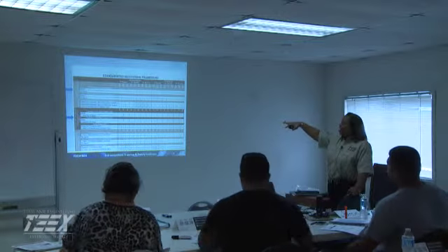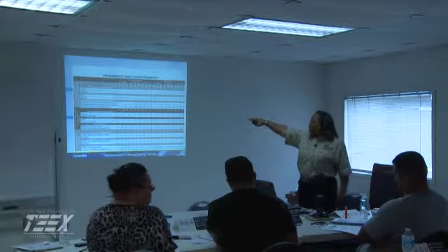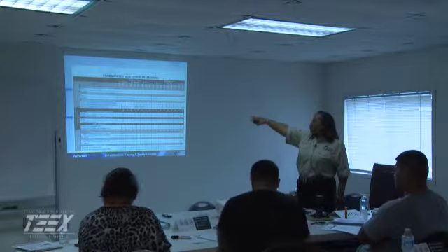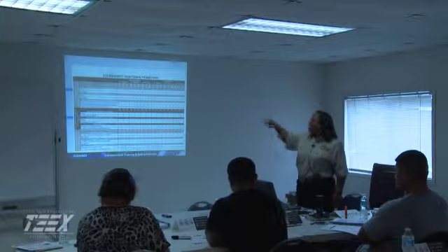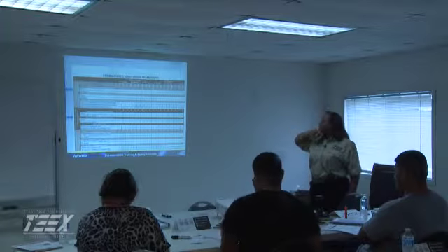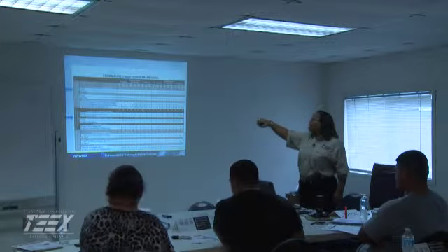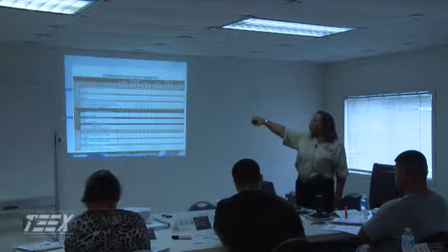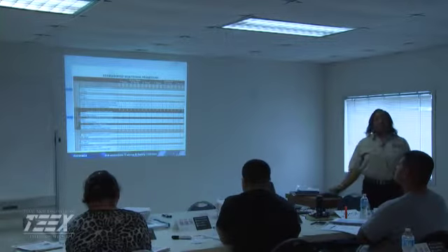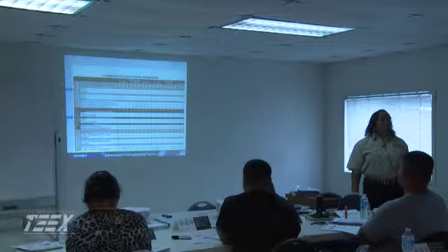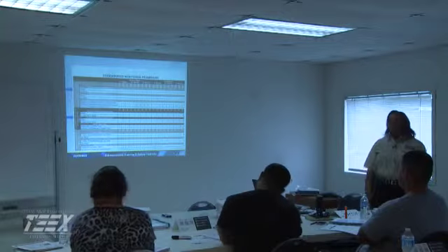And it goes on to show you how to read it. Now, if I have 4 asterisks, for instance, groundwater or surface water that's above the level, notice what happens for my inorganic. If I'm consistently, reliably less than the MCL for a groundwater system, I'm still doing it once every 3 years and once a year for surface. But once I get greater than the MCL, how many asterisks or stars do you see up there? 4. So that means I'm doing that analysis how often? Every quarter. You get the idea.